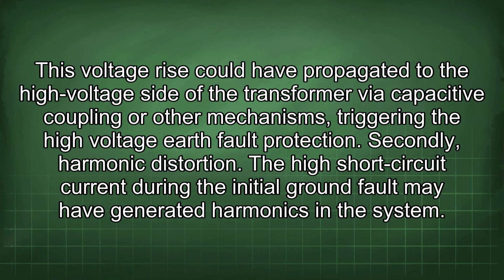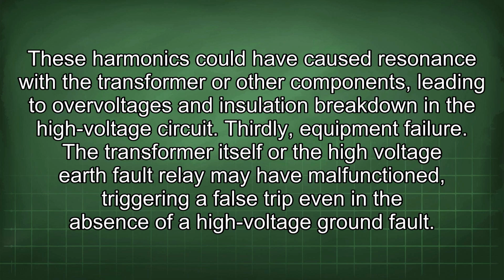Secondly, harmonic distortion. The high short circuit current during the initial ground fault may have generated harmonics in the system. These harmonics could have caused resonance with the transformer or other components, leading to overvoltages and insulation breakdown in the high voltage circuit. Thirdly, equipment failure.